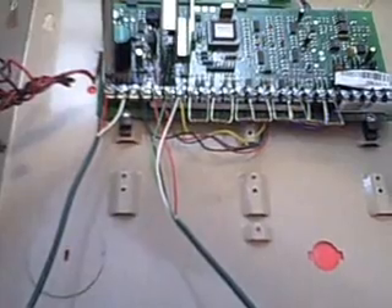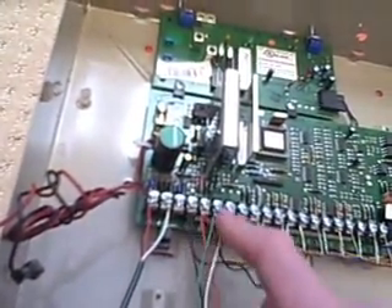We've got a power connection, 24 volts AC, doubled up this conductor because all I had was some 22 gauge wire — this isn't the final install, it'll probably be 16 gauge or so. This is the data wire for the keypad DC circuit and data circuit. Nothing to it — just basically firing it up on the ground here so I can do some programming. All these wireless nodes are in, power's there, resistors are nice and neat, ready to keep all the zones closed and happy.